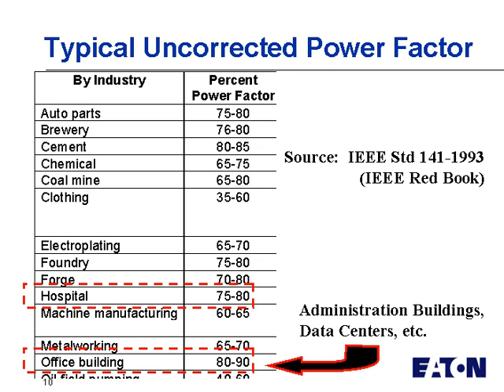This table is taken out of an IEEE source, and this source actually says, for example, for hospitals, a typical power factor that's uncorrected, meaning no capacitors are installed, might range from 75 to 80%. An office building might range from about 80 to 90%, and this would be an example of, for example, administration buildings, data centers, smaller outbuildings that might be on campus. So these are typical numbers that you can expect to see in your facilities.